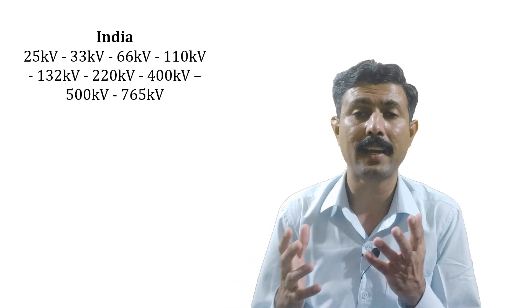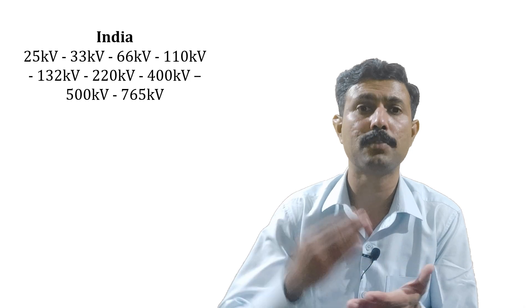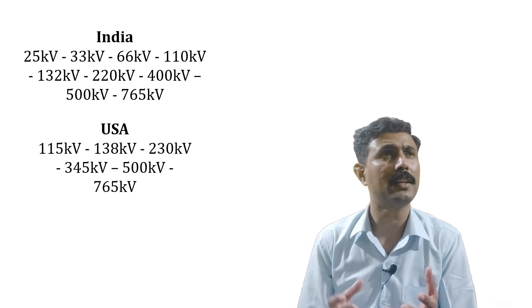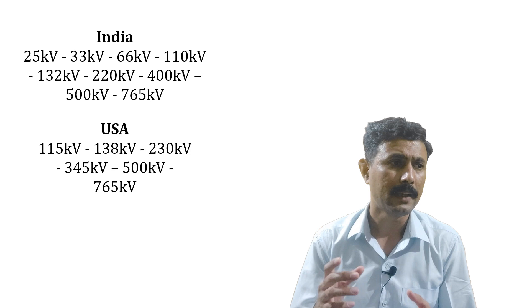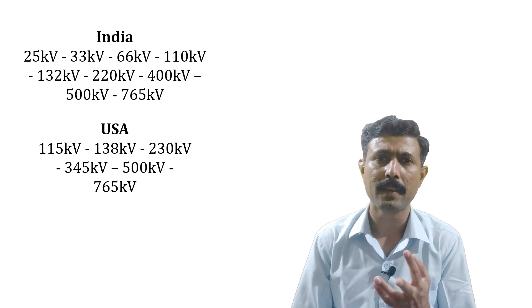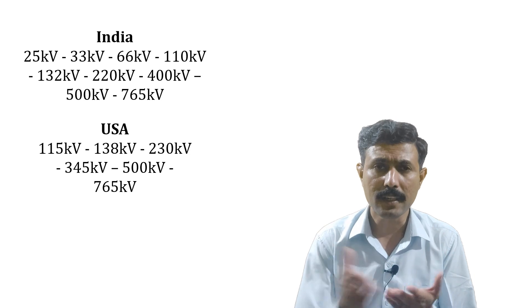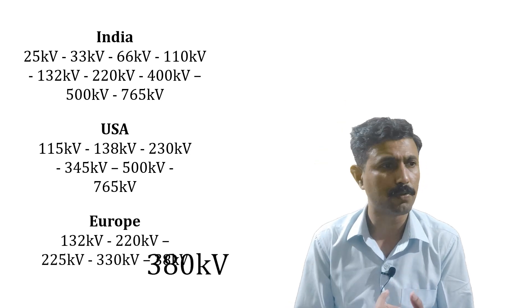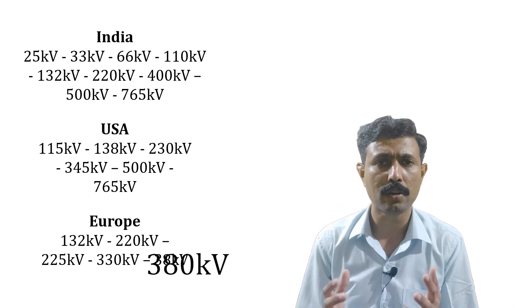If you want true multiples of 11, it should be 440 kV, 550 kV, 770 kV — but that's not what is used. In the USA, they use 115 kV, 138 kV, 230 kV, 345 kV, 500 kV, and 765 kV — not all multiples of 11. Even in Europe, they use 132 kV, 220 kV, 225 kV, 330 kV, and 380 kV. So you can see there is no consistent multiple of 11 across these countries.